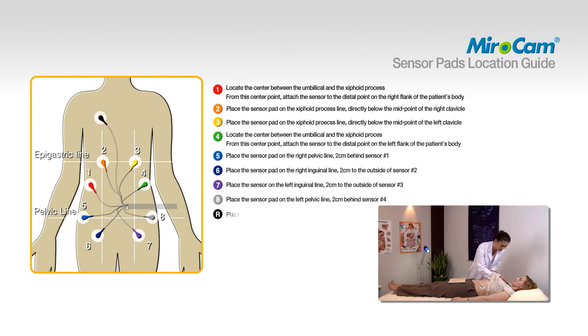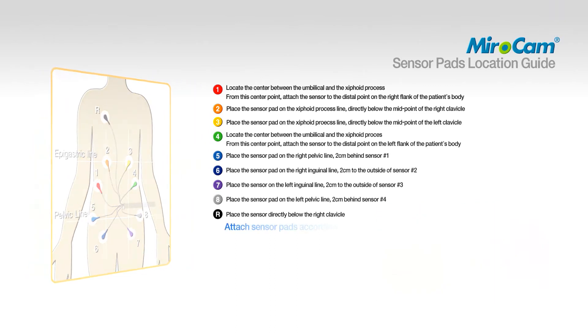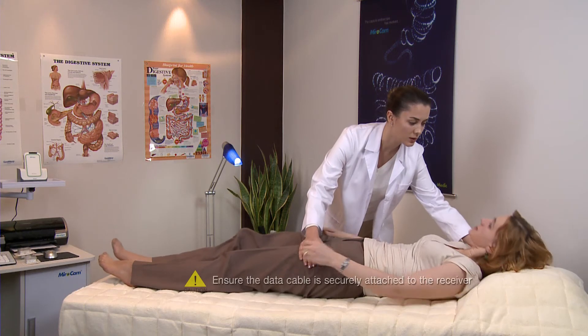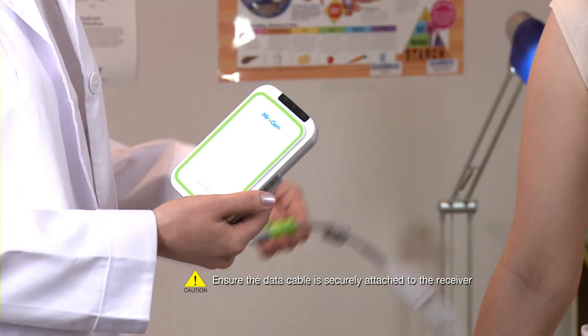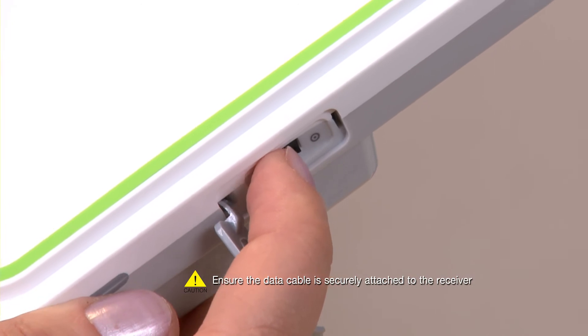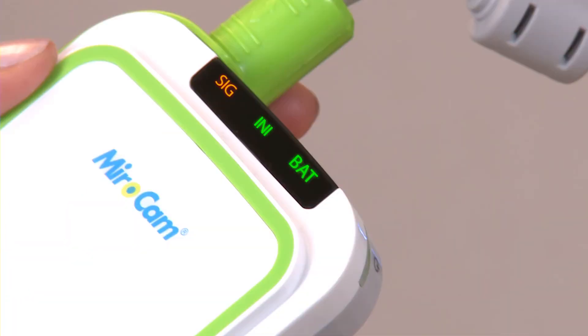To attach pad R, place the sensor directly below the right clavicle. The numbering of the data cables and sensor pad must match the specified area. After attaching the sensor pads, have the patient sit up and connect the data cable to the receiver. Turn on the receiver and check the battery indicator. The SIG icon should be orange, and the INI and BAT icons should be green. If the INI icon is orange, the receiver needs to be initialized. If the BAT icon is orange, the battery needs to be charged.